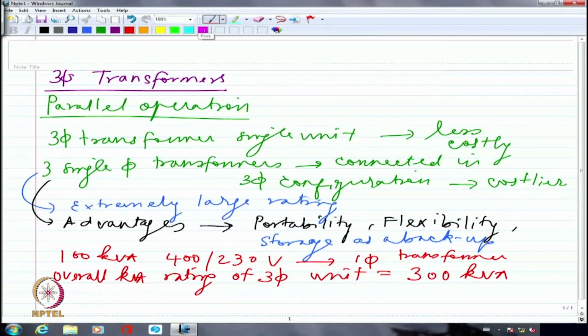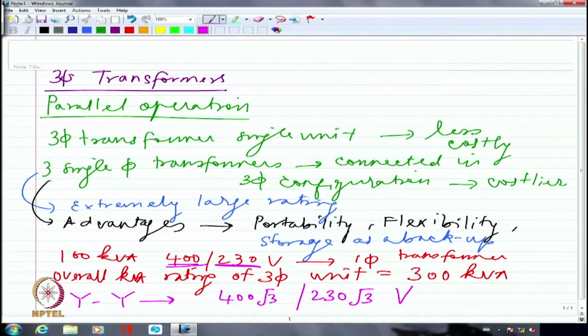And if I am connecting this in star-star configuration, for example, I am going to have again for the star-star three-phase transformer, the kVA rating will be 300 kVA, no doubt. But if I look at the voltage rating, the 400 whatever we are mentioning is per phase. Similarly, the 230 we are mentioning is per phase. So when I am looking at a star connected transformer, it becomes per phase multiplied by √3, because we always mention it in line voltage configuration, not in phase. So I will have to call this configuration 400 multiplied by root 3 divided by 230 multiplied by root 3 volts. So the primary line voltage becomes 400 times root 3 and the secondary line voltage becomes 230 times root 3. So correspondingly I would be able to calculate the current as well.